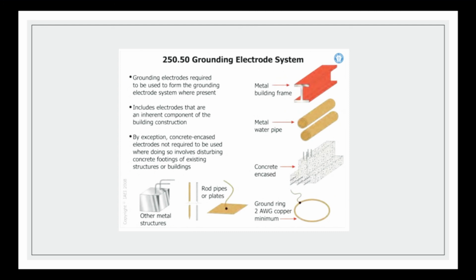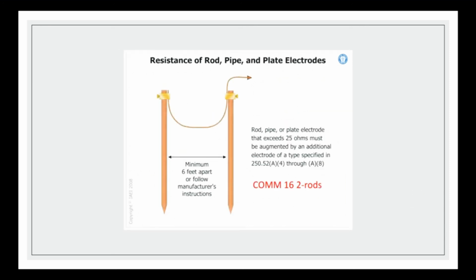Okay, in Article 250 Section 50 about the grounding electrode system, a metal building frame, metal water pipe, concrete-encased electrode, ground ring, rod, pipe, and other metal structures can be used for grounding. Grounding electrodes present are required to be used to form the grounding electrode system, including electrodes that are an inherent component of the building construction. By exception, concrete-encased electrodes are not required to be used where doing so involves disturbing concrete footings of existing structures or buildings. Okay, the minimum distance between two rods is 6 feet apart or follow manufacturer instructions.